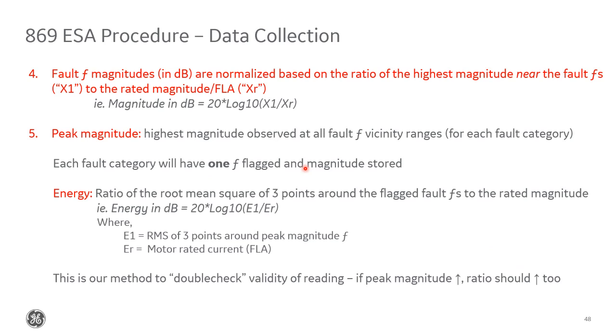Then we normalize that magnitude to the motor's rated full load amps magnitude to make the values conceptually easier to compare. We used to normalize all the signals to the fundamental, but that leaves us susceptible to load variations that'll change that value, whereas the motor's rated FLA will always be constant. So that's basically what we're saying in step 4 here. Take the highest magnitude at each fault frequency and normalize it to the FLA.